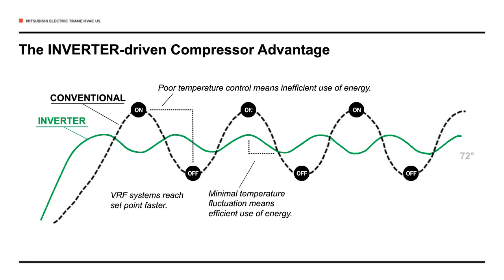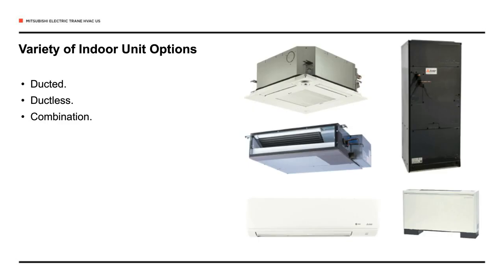So let's talk a little bit about the compressor advantage of VRF systems. Each VRF outdoor unit has an inverter-driven compressor, enabling the system to more successfully handle part load and low load conditions compared to conventional HVAC systems. The system only uses the precise amount of energy to meet the desired set point. The VRF system keeps occupants comfortable at the set temperature they choose, even as environmental conditions change. This efficient approach reduces monthly energy bills and increases occupant comfort.